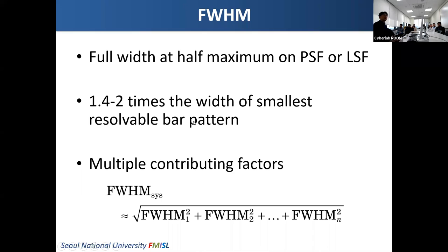If we have multiple contributing factors to the resolution, the system resolution is the convolution — the combination of each component. For example, the system resolution of a gamma camera is determined by the collimator resolution and intrinsic resolution. We can calculate the system FWHM using this equation, where this is the collimator FWHM and intrinsic FWHM.